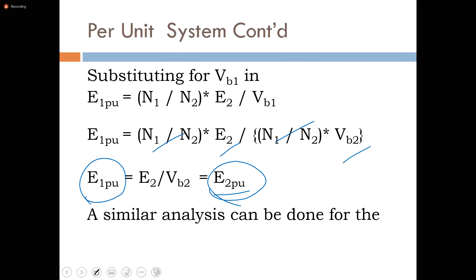Now, earlier, I made mention of the fact that when you bring a piece of equipment into a power system, you'll have to change the per unit value, because the per unit that you get for the piece of equipment will be based on the rating of the equipment. So you'll hear reference being made to per unit on rating or per unit on system base. The per unit on rating is what the manufacturer will give to you. The per unit on system base is when you have now connected that equipment to the network. You have to change that per unit value when you are going to do your calculations.